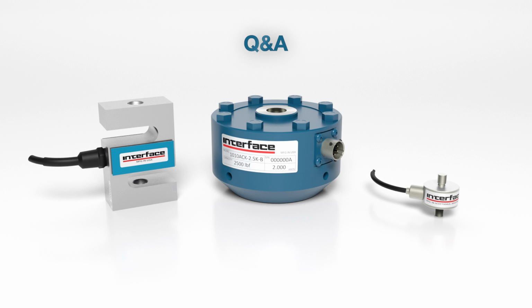Okay, what happens if you use a softer material as a loading surface? You could have damage, but typically what you're going to see is some issues with your linearity and hysteresis. We want things to be nice and stiff so that the load cell is the item doing the deflecting. So that's typically what happens if you're not using proper hardness. Again, it's going to work, but it's just not going to give you the best performance possible.